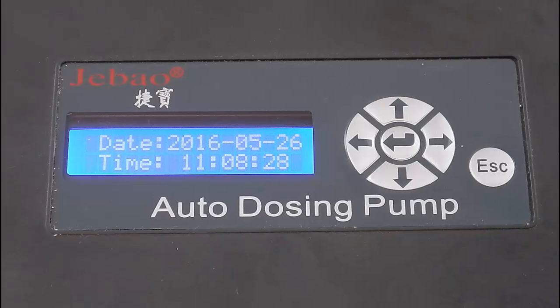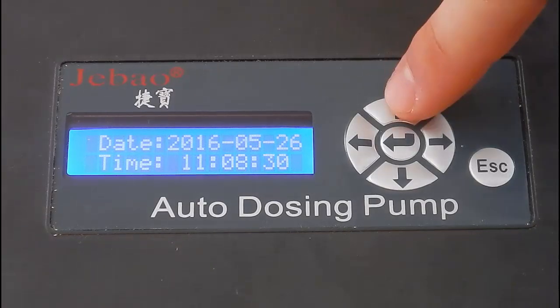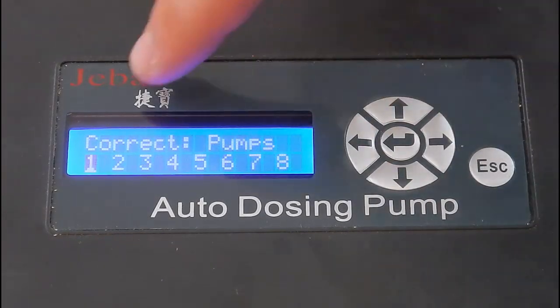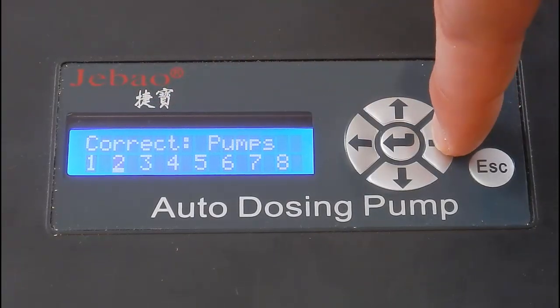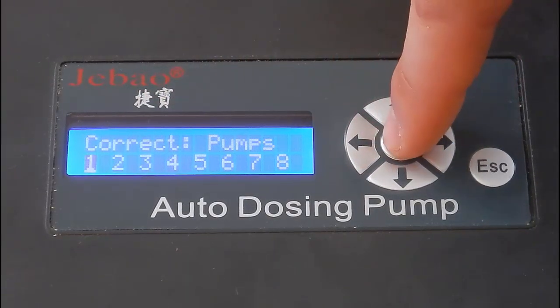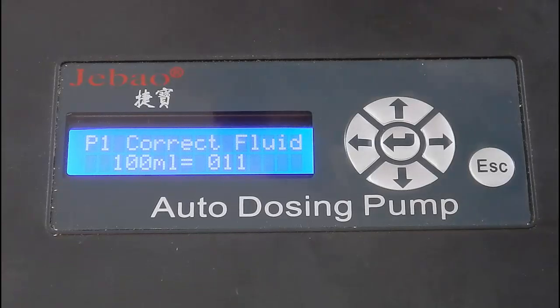To start the calibration process, come to the main screen here. You can hit the top or bottom button, doesn't matter, and you'll see correct pumps, so you can select whatever pump you want. We're on pump 1, go ahead and hit enter. Now you can see it says 100 milliliters equals 0.11.